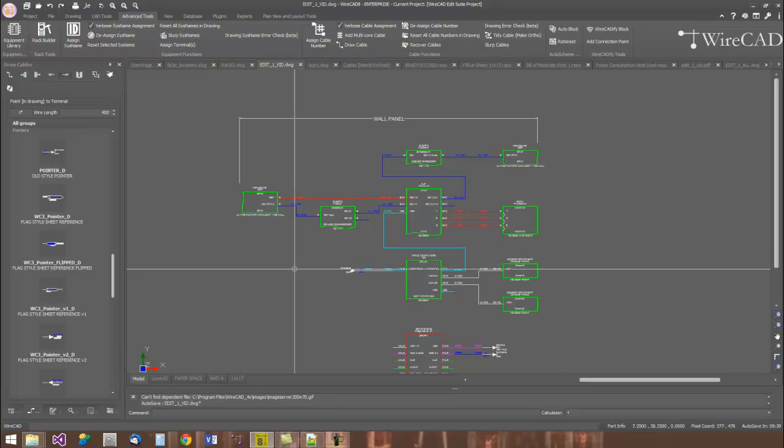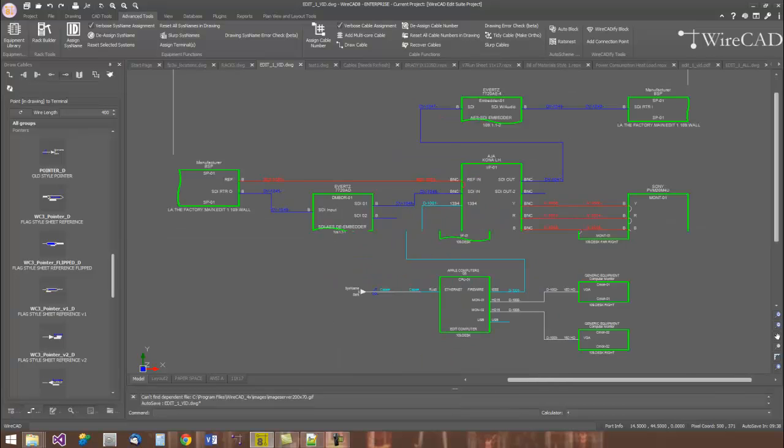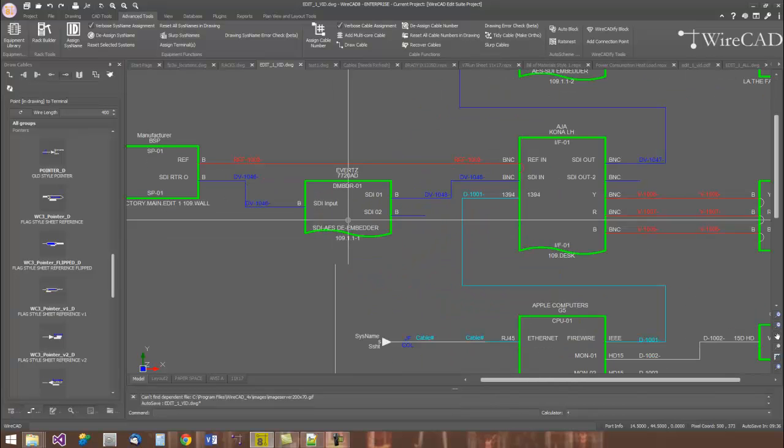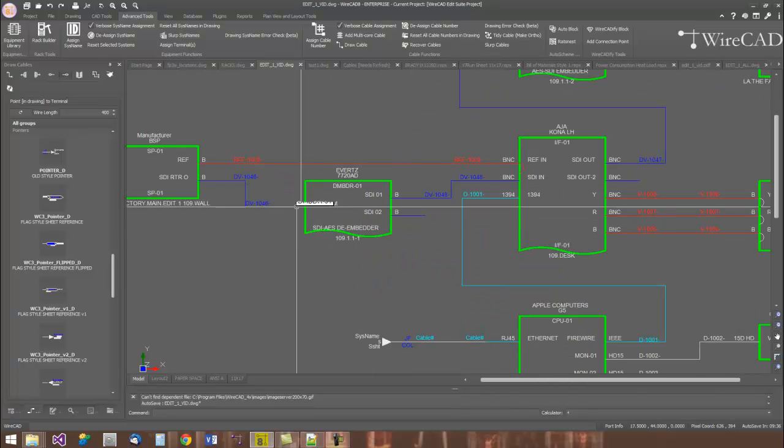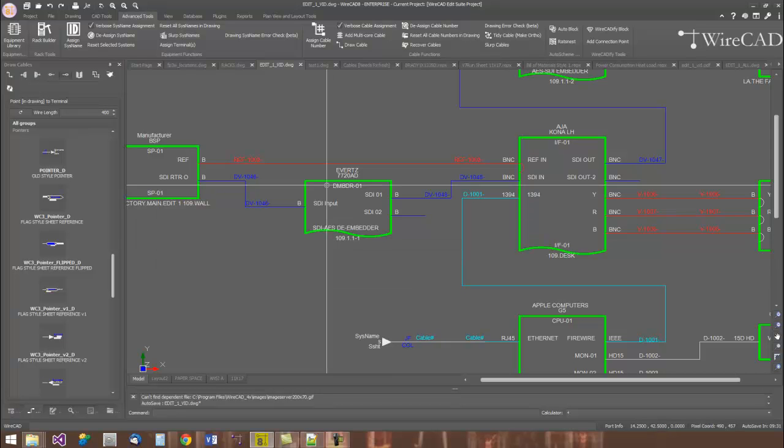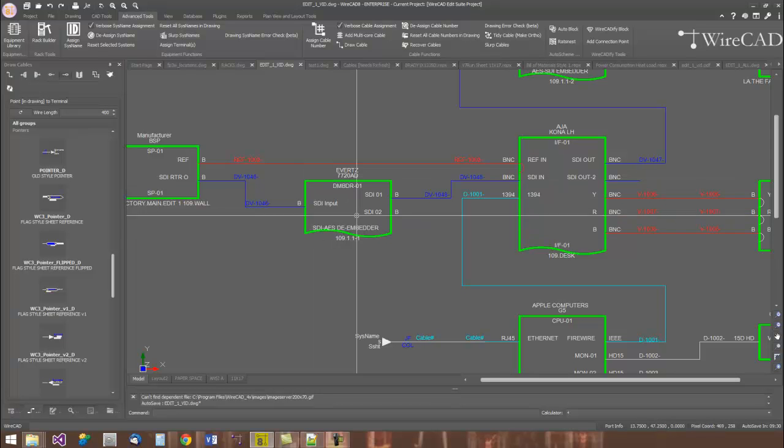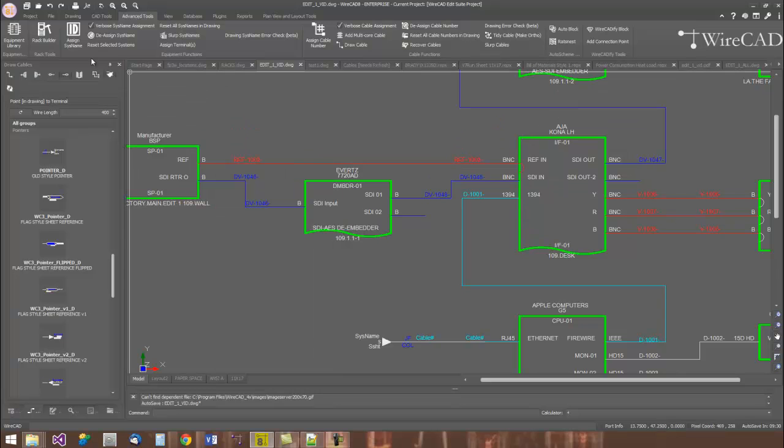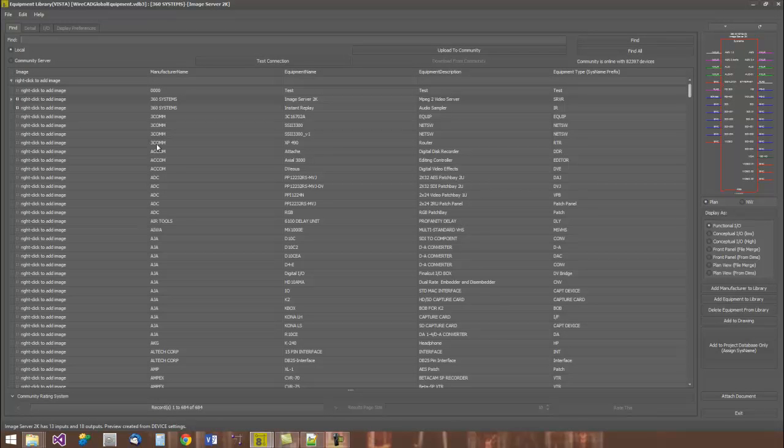Rather than you having to make a CAD decision as to whether or not or how you might draft this particular functional block for this diagram, we use our equipment library to generate this object automatically. The equipment library is a database of equipment definitions. Who makes the device, what it's called and what it's I/O.